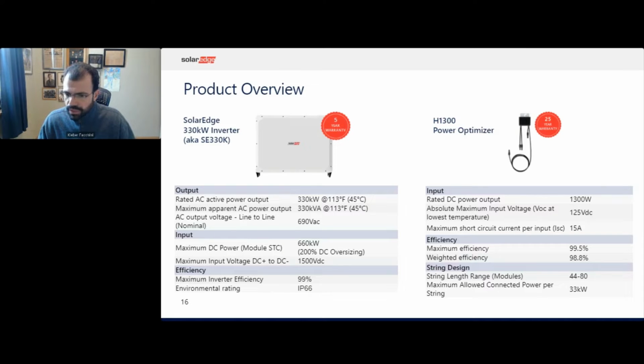1500 volt DC design supporting ground mount and carport applications. Okay. Now on the optimizer side, each optimizer is connected to 2 solar modules, each with maximum power 650 watts. So that's the 1300. So you can use modules up to 650 watts. This optimizer supports panels with a short circuit current up to 15 amps. And here is where I wanted to make sure that everyone understands the source of the balance of system benefits.